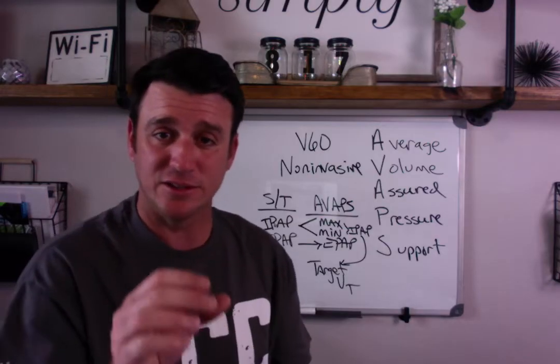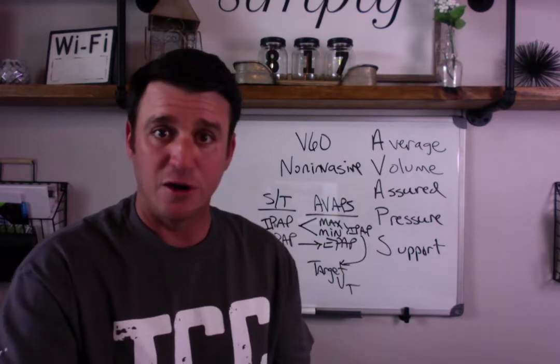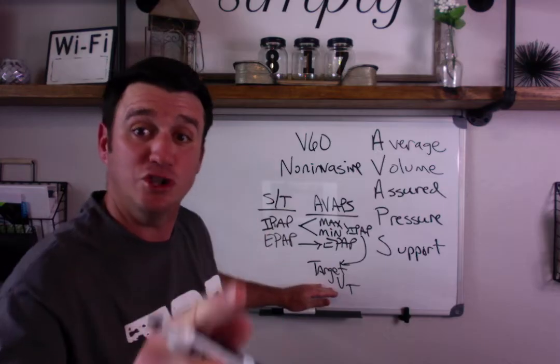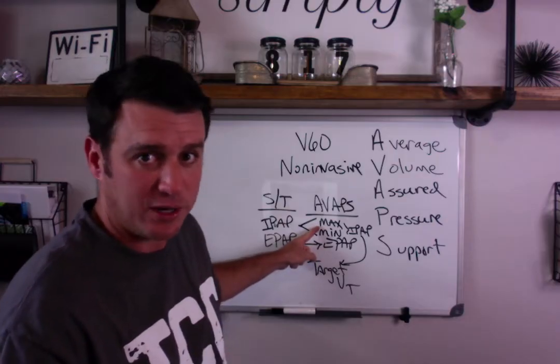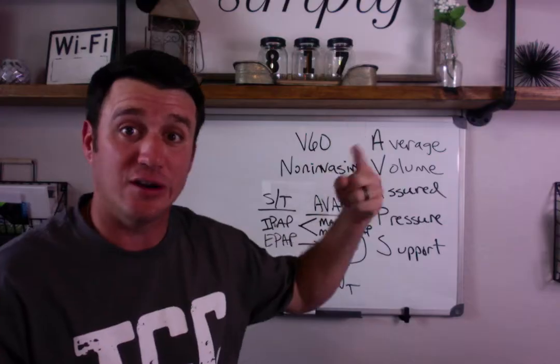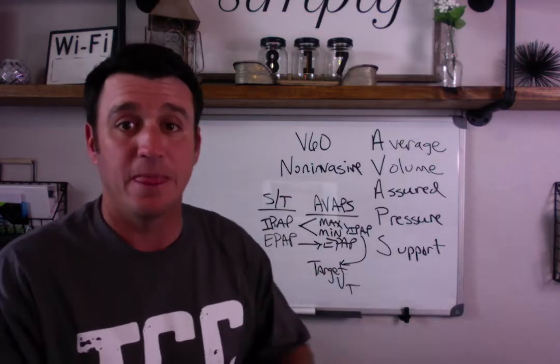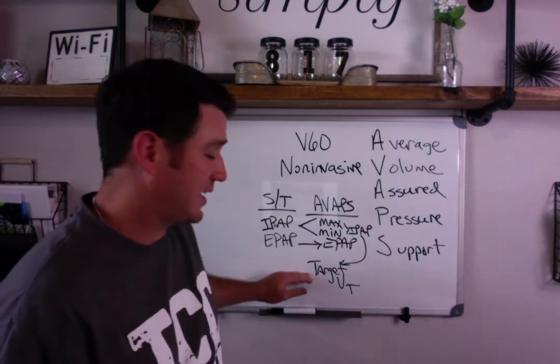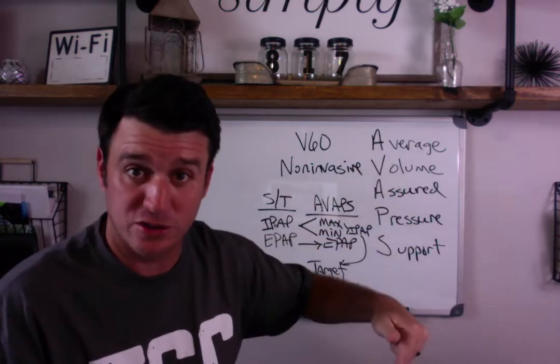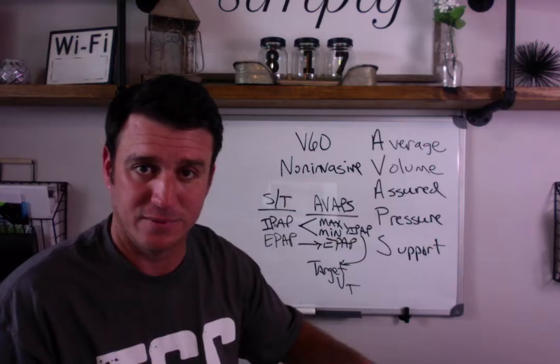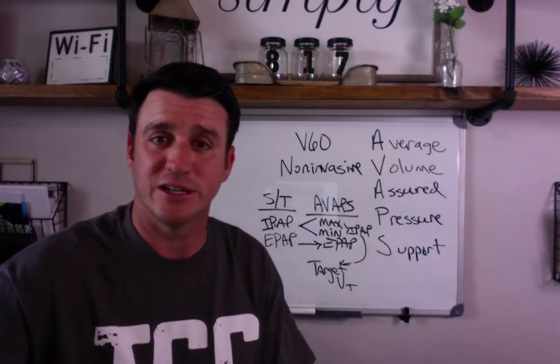That target tidal volume is important because it tells the V60: if the patient's average tidal volume falls below the target tidal volume, incrementally increase the IPAP, which will incrementally increase pressure support, which should result in a larger tidal volume, hopefully bringing you close to the target. Conversely, if the average tidal volume over a measured time comes back greater than the target, the machine decreases IPAP, decreasing pressure support, resulting in a smaller tidal volume — hopefully closer to the target, which helps sustain a target minute ventilation.